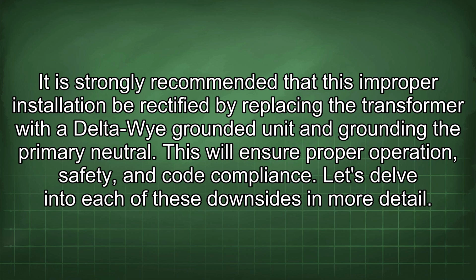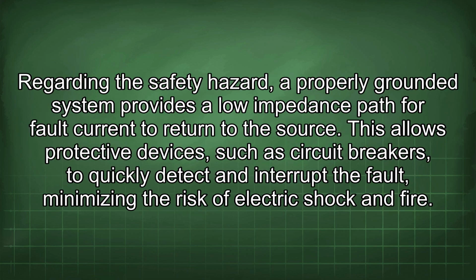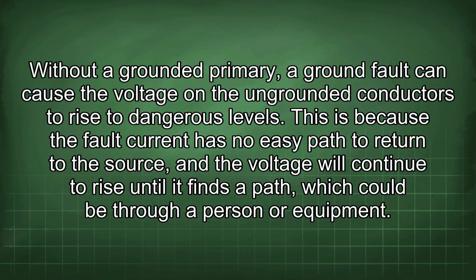Let's delve into each of these downsides in more detail. Regarding the safety hazard, a properly grounded system provides a low impedance path for fault current to return to the source. This allows protective devices, such as circuit breakers, to quickly detect and interrupt the fault, minimizing the risk of electric shock and fire. Without a grounded primary, a ground fault can cause the voltage on the ungrounded conductors to rise to dangerous levels. This is because the fault current has no easy path to return to the source, and the voltage will continue to rise until it finds a path, which could be through a person or equipment.